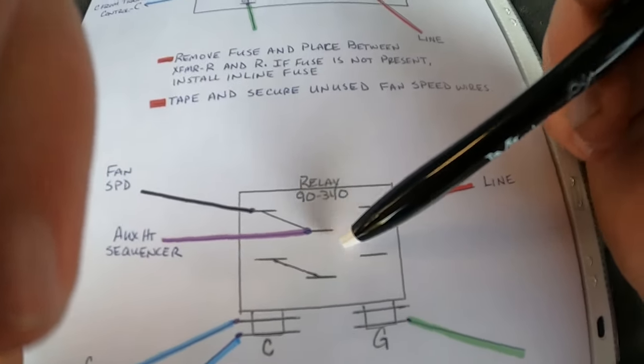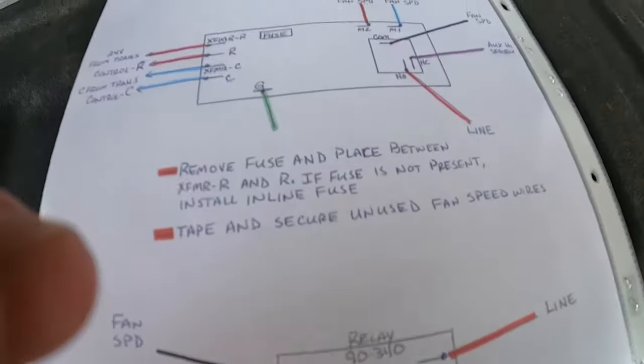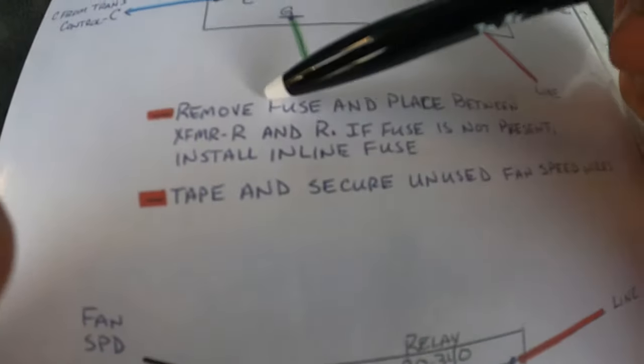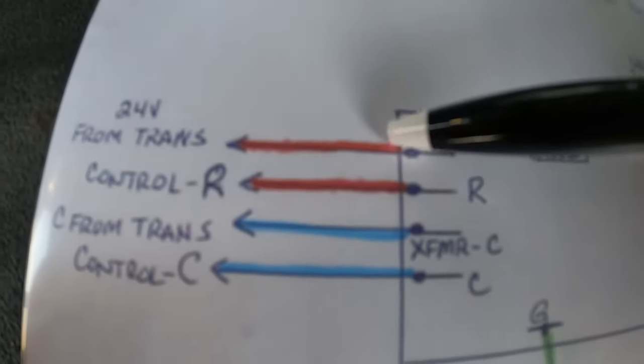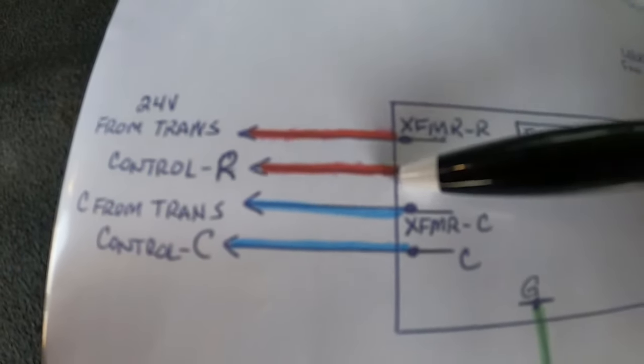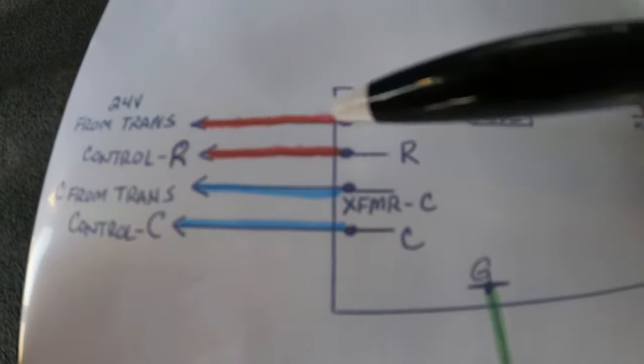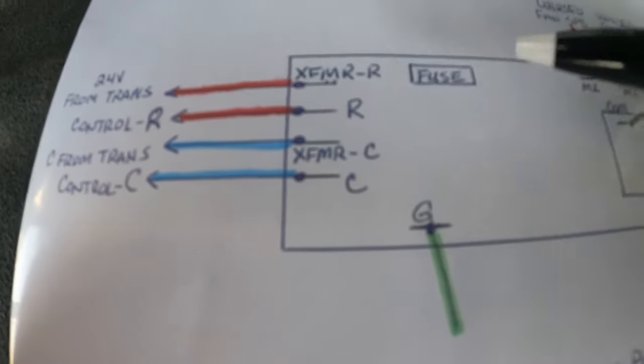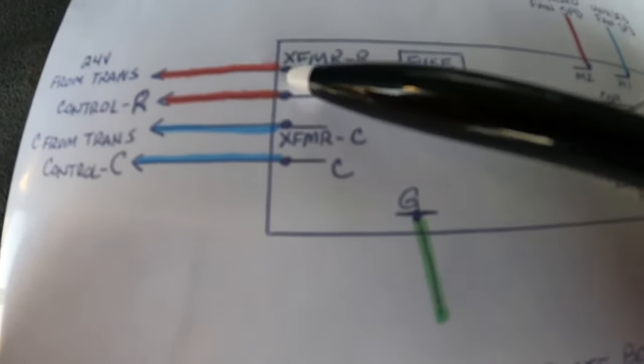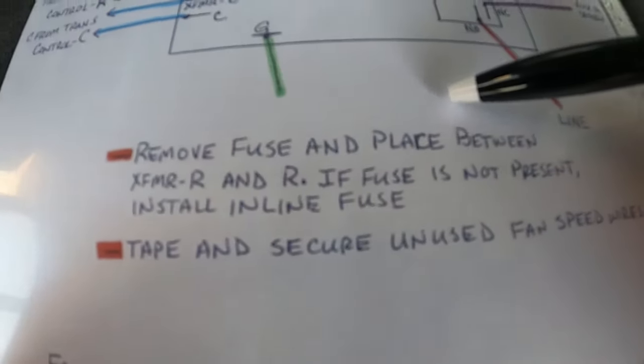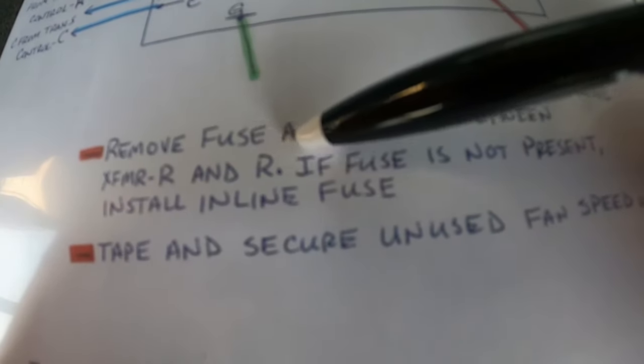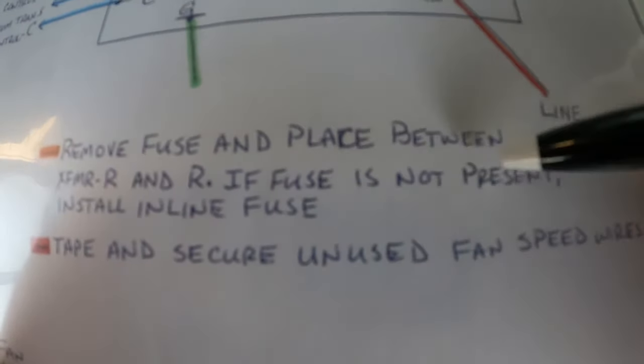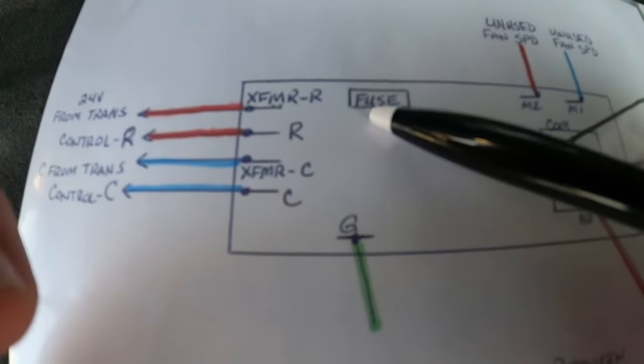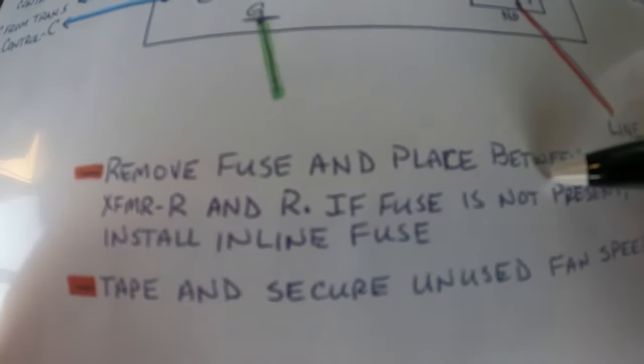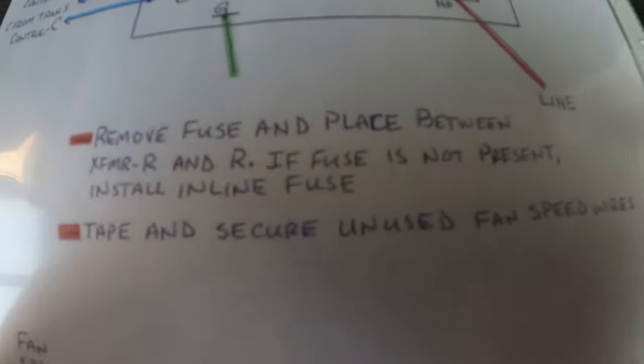How would you replace that with this particular relay? First of all, it tells you right here, you're going to remove the fuse here off the board. You're going to take these two 24 volts from your transformer and your 24 volts out back to your controls and your thermostat. You're basically just going to disconnect those two, and then you're going to place that fuse in between them. Remove fuse and replace between your transformer R and your control R. If the fuse is not present, because some of these boards didn't come with a fuse, simply install an inline fuse.